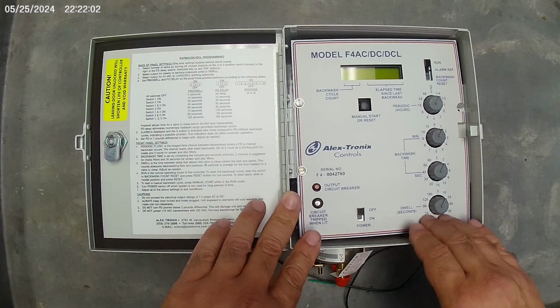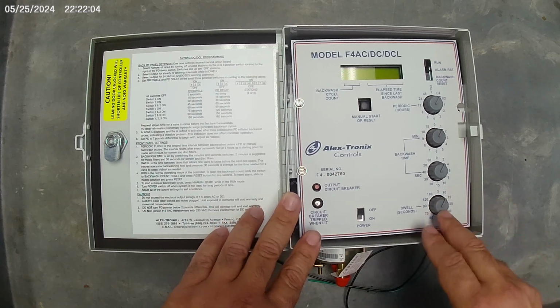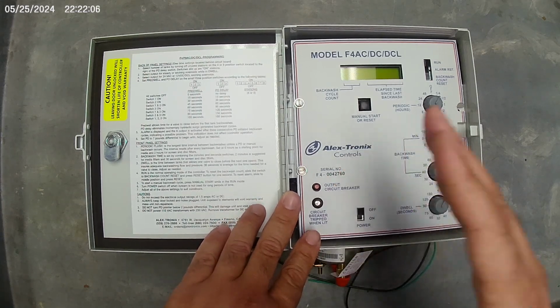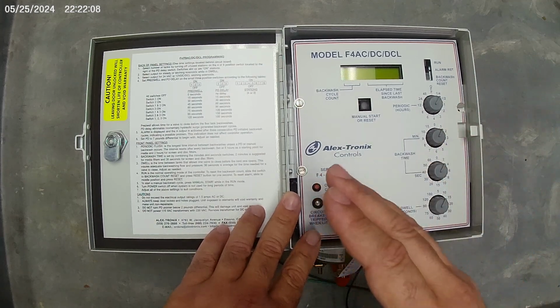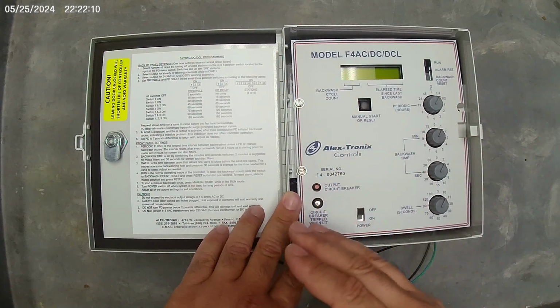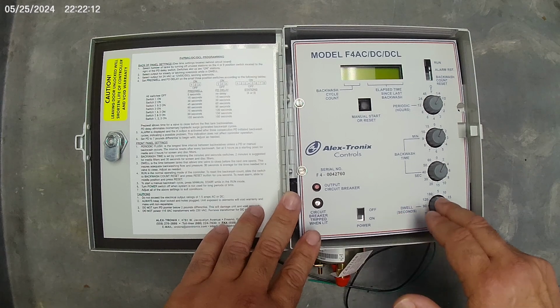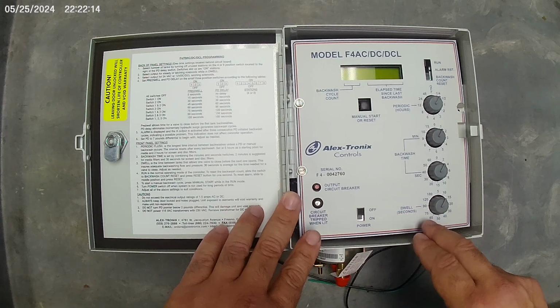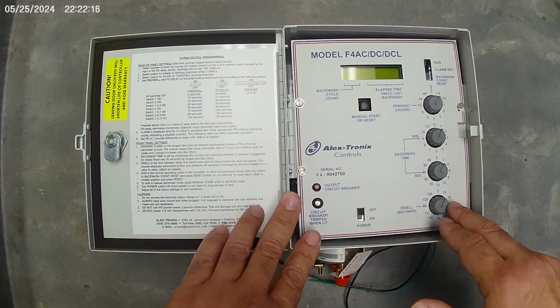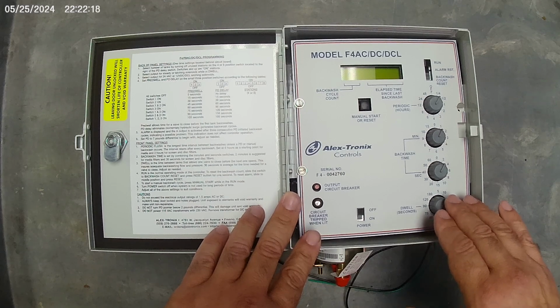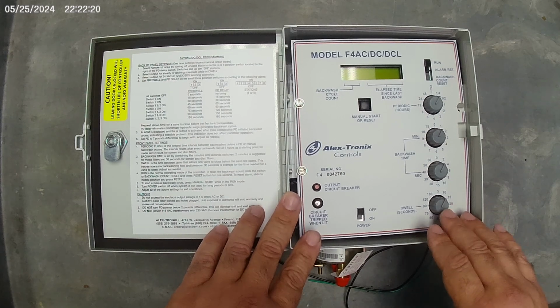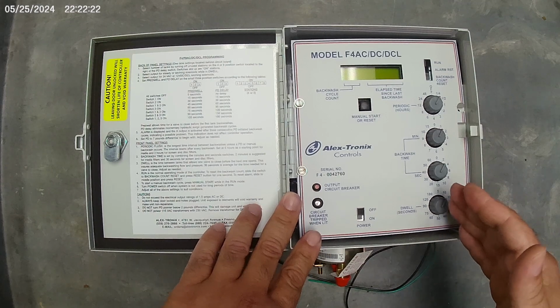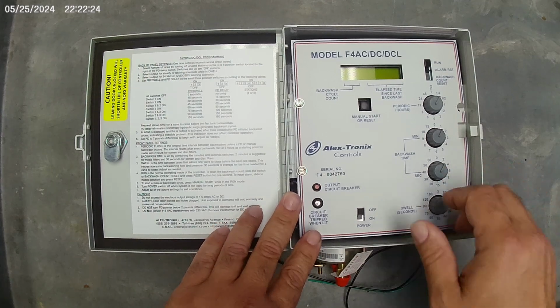And then dwell is the amount of time in between filter tanks. So if you have a valve that takes a long time to open or close, you want to make sure that the dwell is at least as long as that valve takes to operate. For most large systems, 10 or 15 seconds would be a typical time to allow the valves to transition.